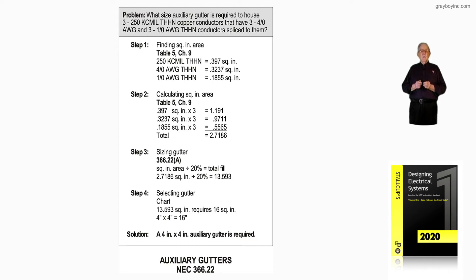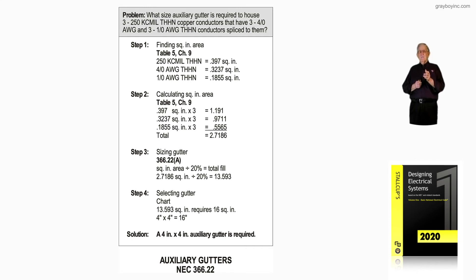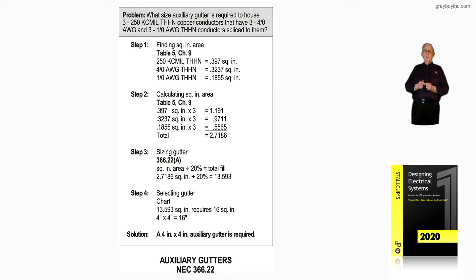Step two: we have to multiply those square inch areas for each size conductor by the number — there happens to be three for each one. So when we do the math from the cross-sectional areas selected from Table 5, Chapter 9, and total them, we come up with 2.7186 square inches, as seen in the quick calc.